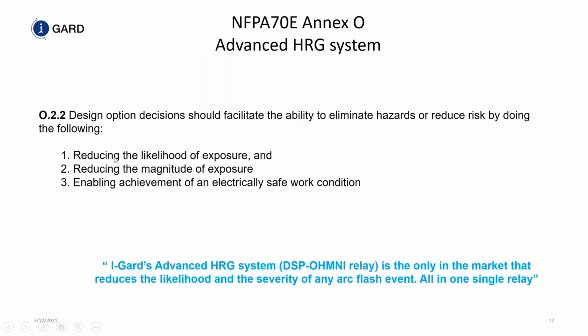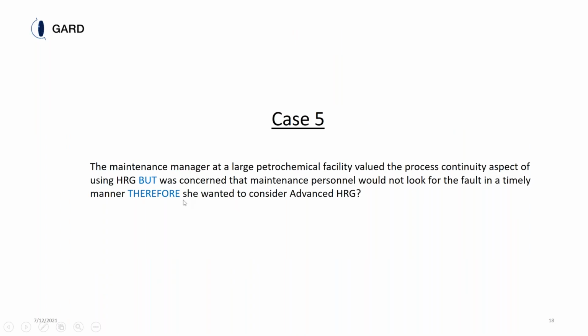When we do this, we reduce the likelihood of exposure. NFPA 70E and Z462 both credit high resistance grounding as an arc flash mitigation technique, but it doesn't lower the incident energy. By employing the arc detection module, we also reduce the magnitude of exposure, enabling a safe work condition.